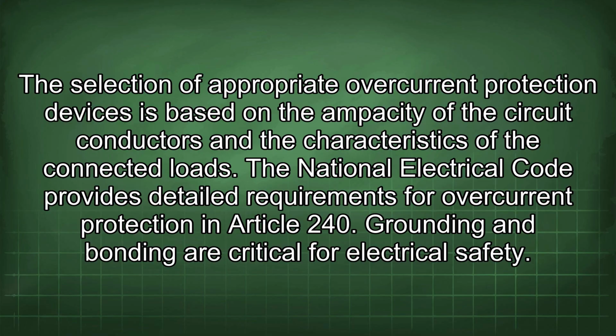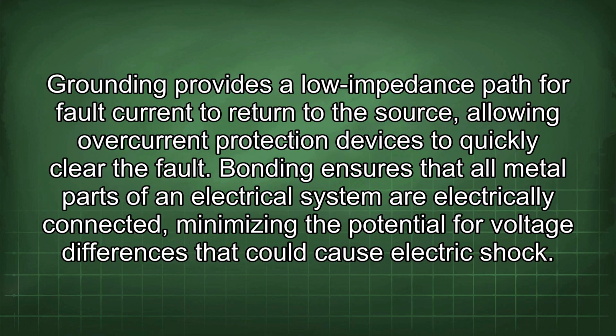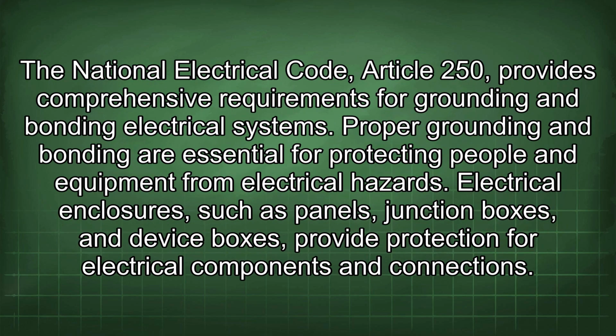Grounding and bonding are critical for electrical safety. Grounding provides a low impedance path for fault current to return to the source, allowing overcurrent protection devices to quickly clear the fault. Bonding ensures that all metal parts of an electrical system are electrically connected, minimizing the potential for voltage differences that could cause electric shock. The National Electrical Code, Article 250, provides comprehensive requirements for grounding and bonding electrical systems. Proper grounding and bonding are essential for protecting people and equipment from electrical hazards.